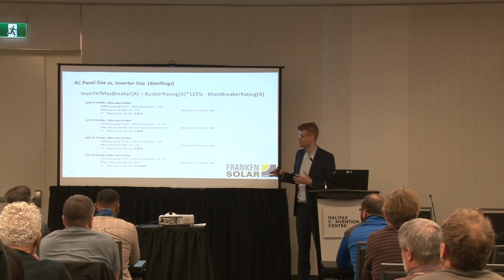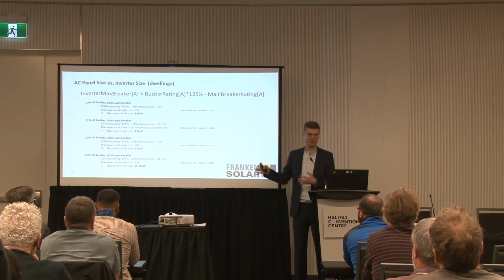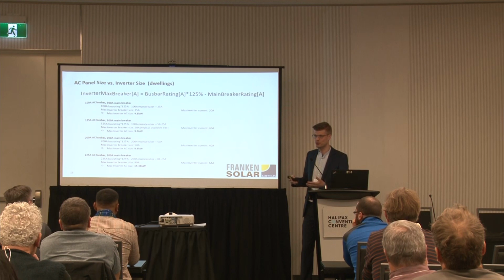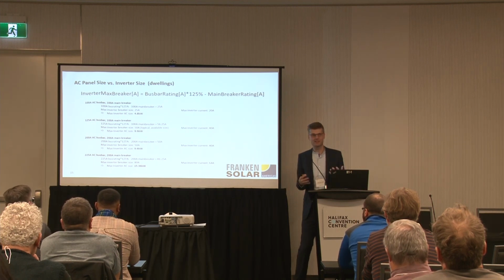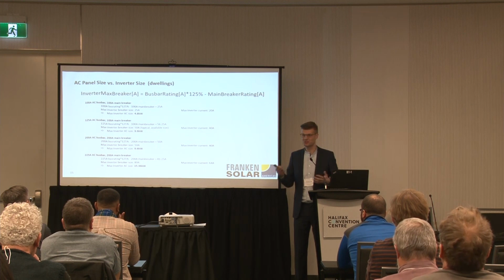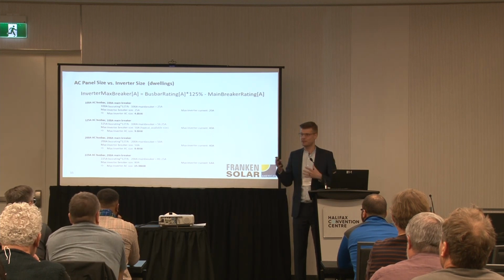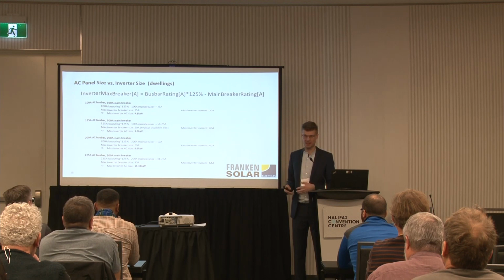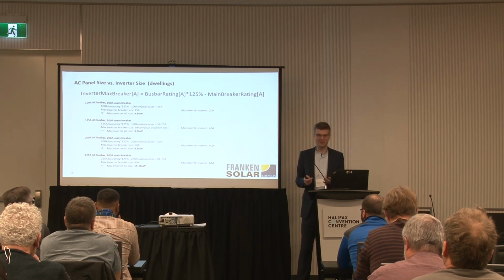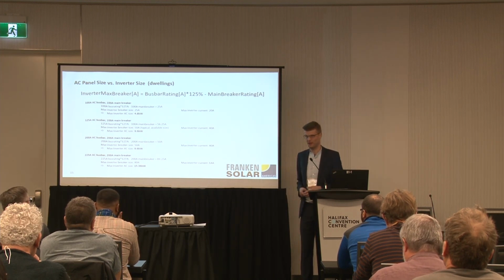When it comes to oversizing in general, you saw the crazy numbers up to 31 kilowatts. That's not something I would recommend, and there are also certain limits from a code perspective that do not allow that today with current panels and the higher amperages these new higher wattage panels actually have. But my main message is to take that as an idea to go back to your simulation tool and try out systems you already have or systems you're designing for customers, and maybe put a bigger or smaller inverter in, or more solar or less solar, to get a feeling for how the impact would be on the yield for your specific designs, and how you can utilize that to be more competitive in the market, maybe against other companies you're competing with, or just to save the customer additional money for not really any value if you upgrade the electrical panel for them just because they want to have solar.